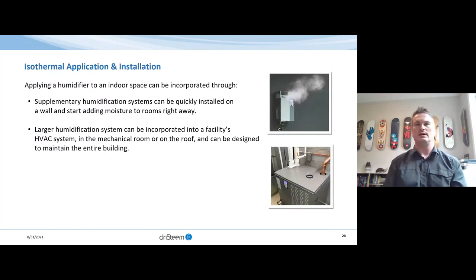An application of an isothermal system can be indoors, mounted on a wall and directly applying the steam in the localized space. The benefit to that is you get a very immediate effect. You're not reliant on the incoming air conditions and other factors that come with your HVAC system. You're really looking at the temperature in the room environment directly as it's being applied. Larger systems can be incorporated into the HVAC system centrally, either mounted in a mechanical room, on a rooftop, or other locations. And it can be incorporated into maintaining the entire building's relative humidity.